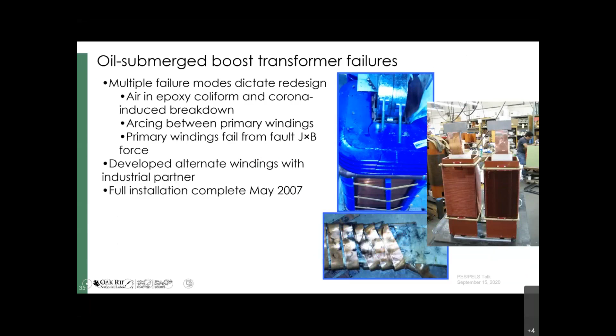The winding for the secondary was made by the company that built the modulator. It was a cast epoxy winding, and unfortunately it had air bubbles in it as well. And so we had some instances where it arced through, and there was enough energy involved in the arc to actually crack the case. So finally, we worked with a company out in California, which is famous for pulse transformer development, and we created our own design, which is shown over here on the right. Those have been installed since 2007, and they've actually been running quite well also.